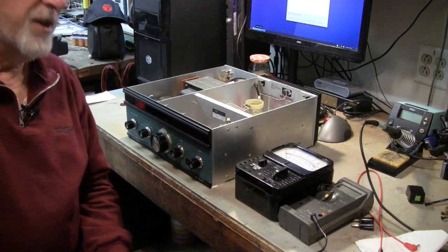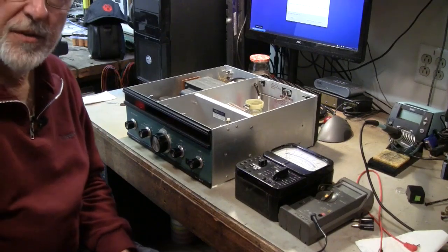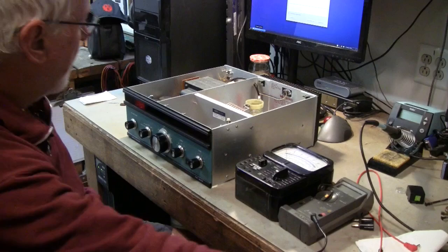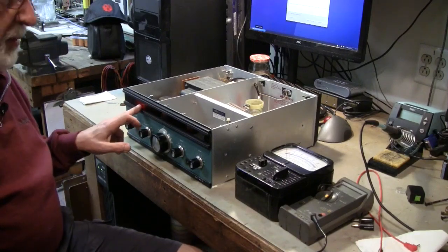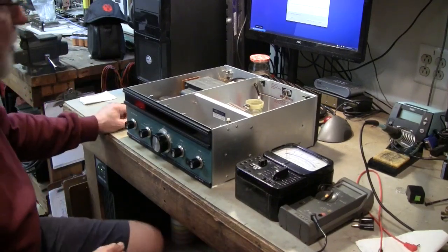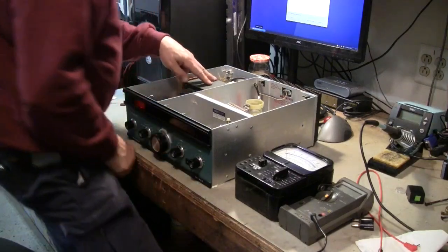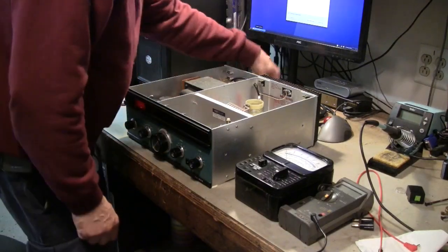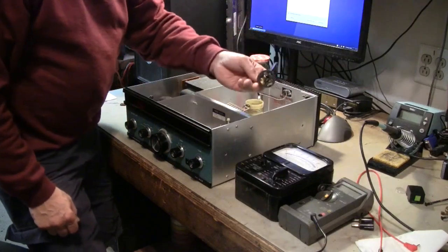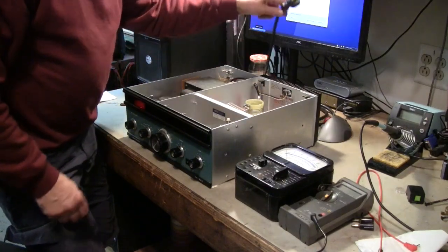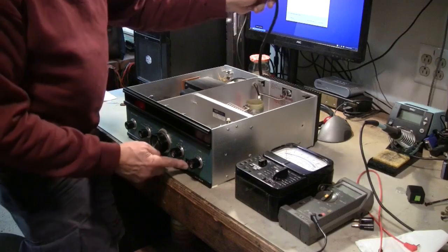The last thing I want to check is the high voltage supply, to make sure it's producing the correct amount of voltage and that the meter itself is calibrated properly. I've already pre-wired the input to the transformer for 120 volts and put the correct plug on the end of the AC cord.